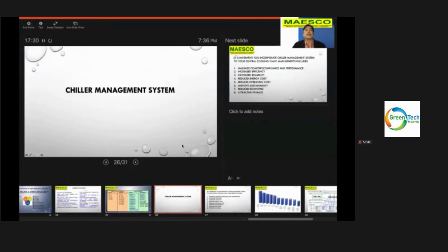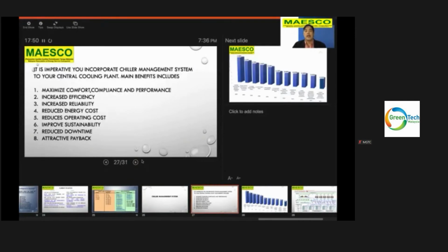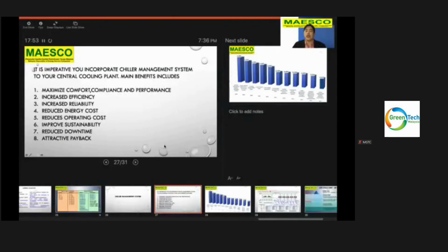Now let's come to the last segment. The last segment is the chiller management system. If you buy a very expensive chiller, very expensive pumps and cooling towers, but you do not have the brain to control each and every one of these equipment, you're down to square one. So it's always good to invest in a very good chiller management system. It's imperative you incorporate a chiller management system into your central cooling plant. The main benefits include maximize comfort, compliance, and performance, increase efficiency, increase reliability, reduce energy costs, reduce operating costs, improve sustainability, reduce downtime, attractive payback. All these are the main benefits.